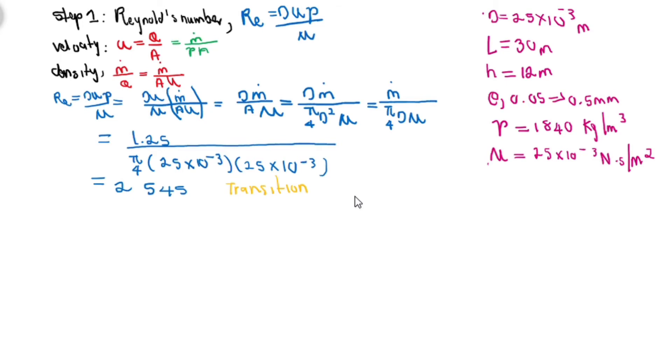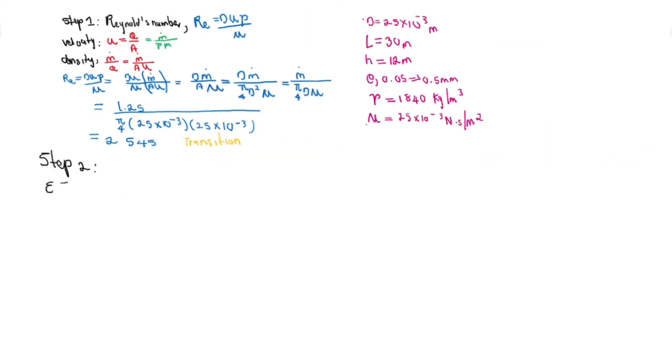Step 2 will be to calculate the relative roughness. We are given the roughness between 0.05 millimeter and 0.5 millimeter. In order to calculate the friction factors, we first have to calculate the ratio between the roughness and diameter. I'm going to calculate it at these two ranges: 0.002 and 0.02. Of course, it's unitless because the units will cancel out.